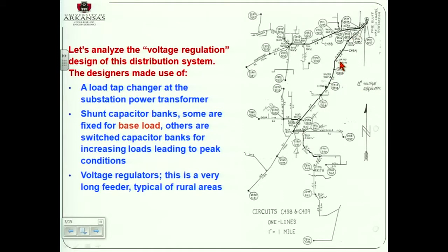But there you see, here there are 1, 2, and we don't have anything, right? I don't see any. And look at that. There are no capacitors. Oh no, here there is one. Right, here is another one. There. Seems to be 100 kVAR, far away from this, so basically there is no step increase.